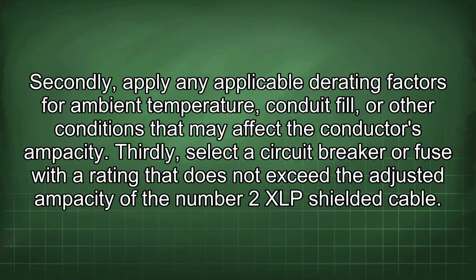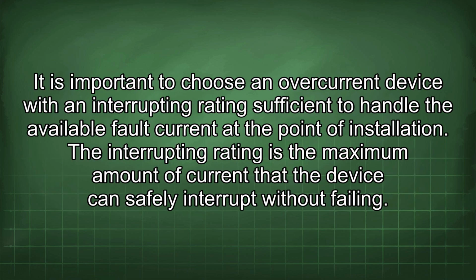Secondly, apply any applicable derating factors for ambient temperature, conduit fill, or other conditions that may affect the conductor's ampacity. Thirdly, select a circuit breaker or fuse with a rating that does not exceed the adjusted ampacity of the number 2 XLP shielded cable. It is important to choose an overcurrent device with an interrupting rating sufficient to handle the available fault current at the point of installation. The interrupting rating is the maximum amount of current that the device can safely interrupt without failing.